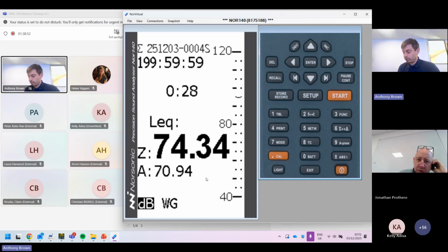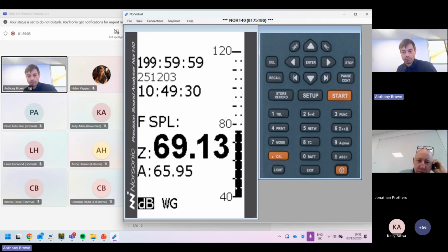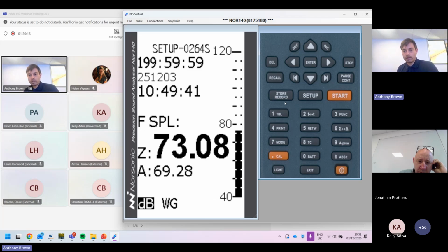And I would recommend just saving your measurement setup. Martin, if you can do that, press the store record key. This might not work for the setup, so just press the exit first. So use this exit key just to clear what's on the screen. So it's just on this standby, just bouncing around. And when you've got to that, so that was the exit key just to clear what's on the screen. Then just press the store record key, this one here, to save the setup file. And going forward, I will load the one that's number 264.